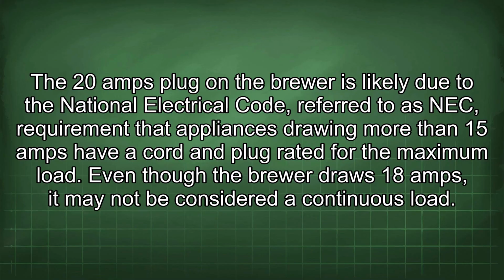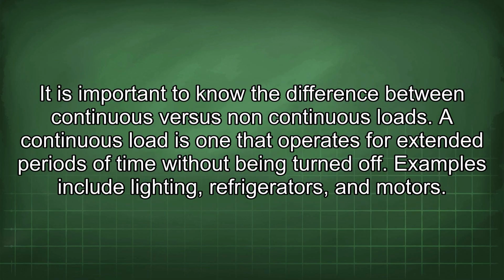20 amps plug on the brewer is likely due to the National Electrical Code, referred to as NEC, requirement that appliances drawing more than 15 amps have a cord and plug rated for the maximum load. Even though the brewer draws 18 amps, it may not be considered a continuous load. It is important to know the difference between continuous versus non-continuous loads.